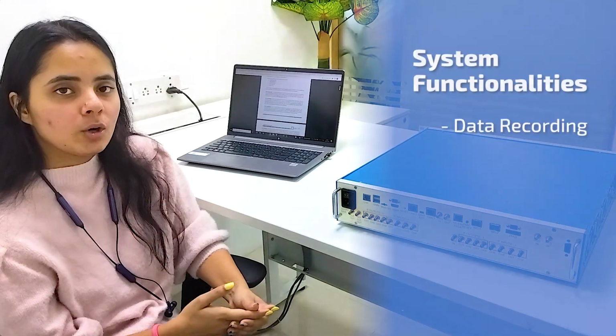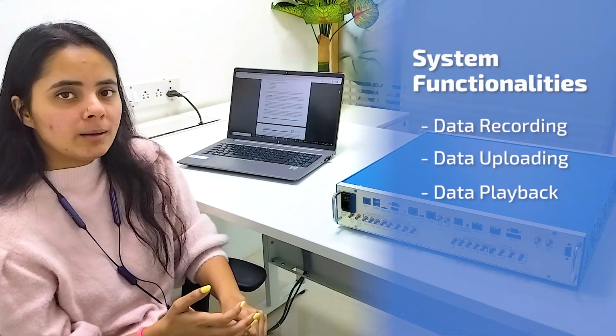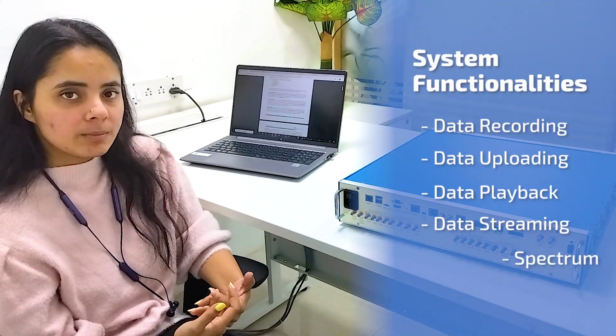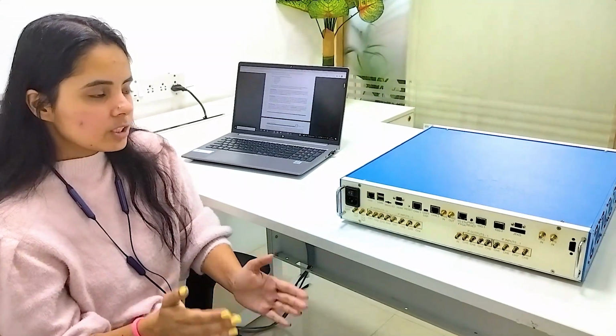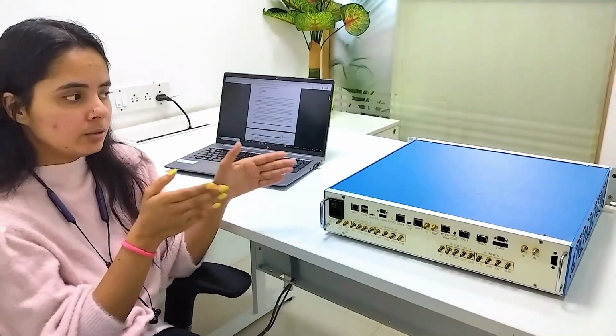So the system mainly offers 5 basic functionalities: data recording, data uploading, data playback, data streaming, and spectrum. The first functionality is data recording. We'll be capturing the live data from the sensors and storing it into the hard disk of the system. Here you can see we have 16 ADC channels. That means all the 16 channels can be recorded and stored into the hard disk of the system at the same time.